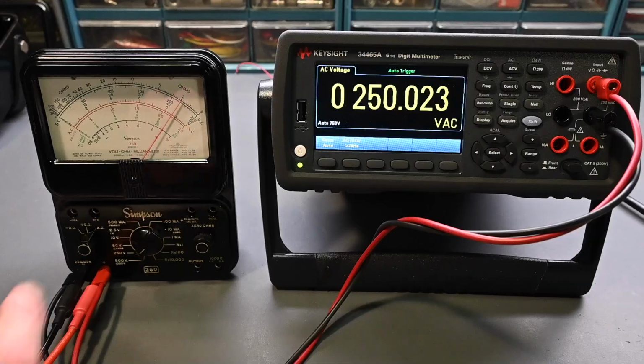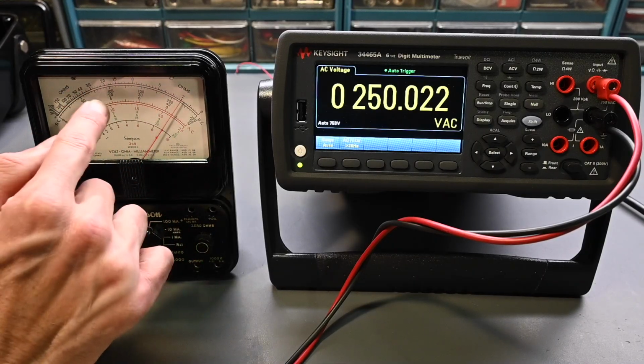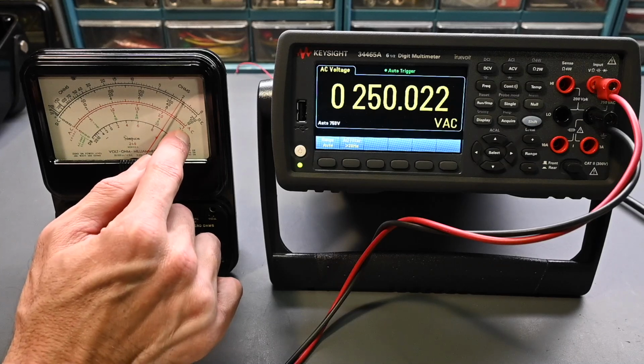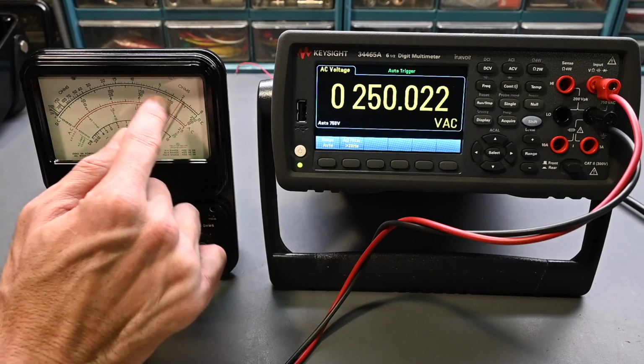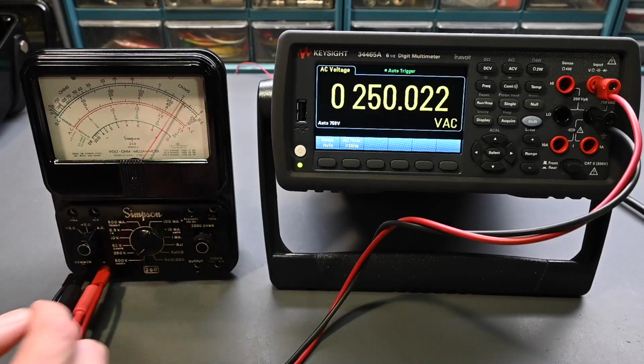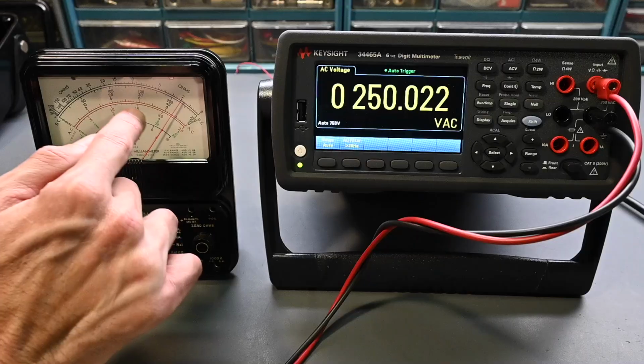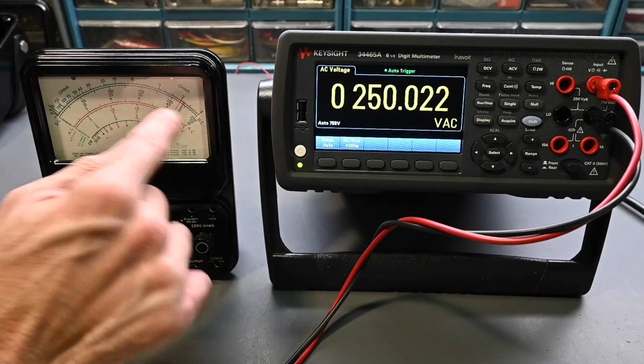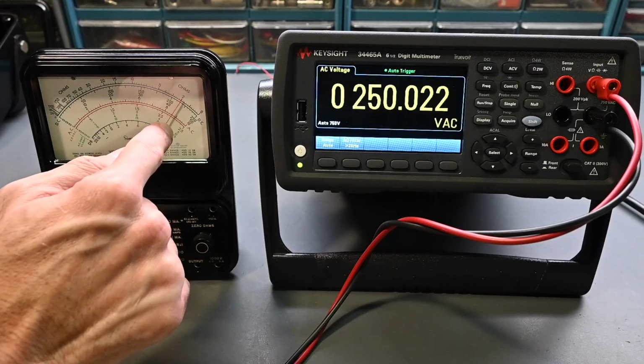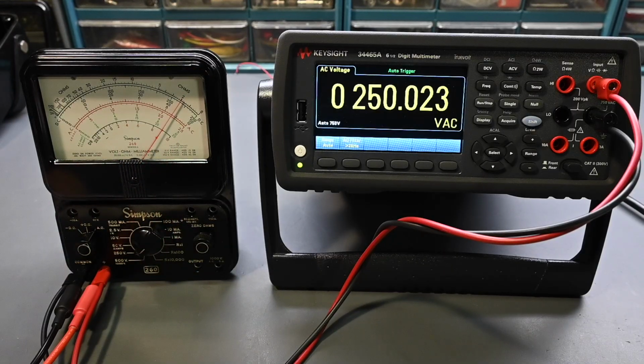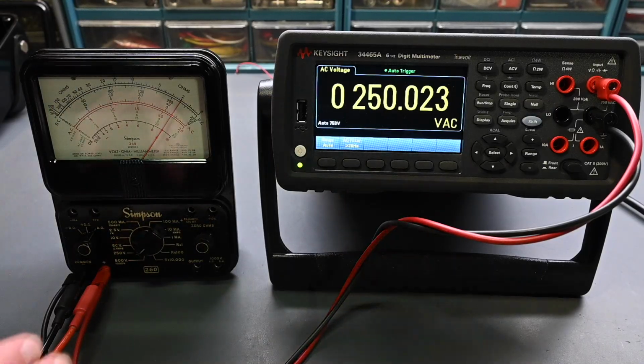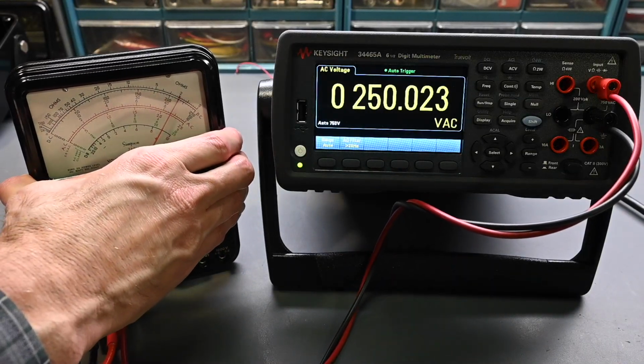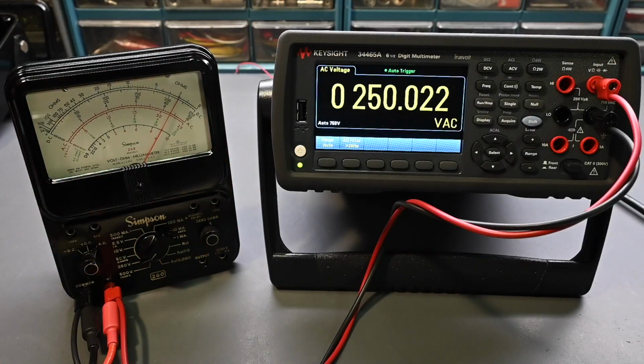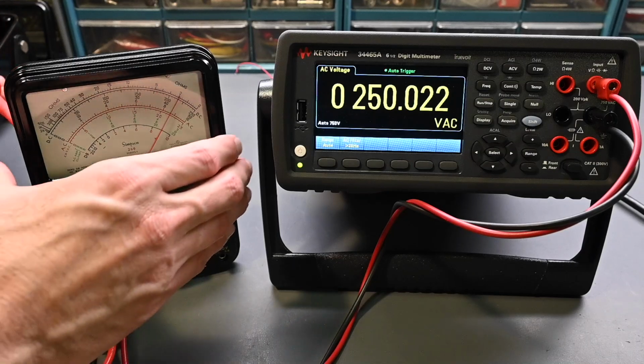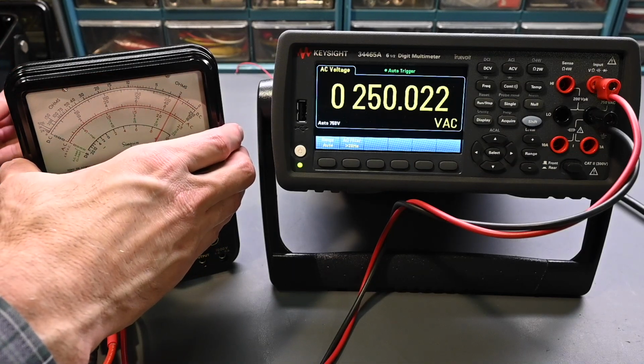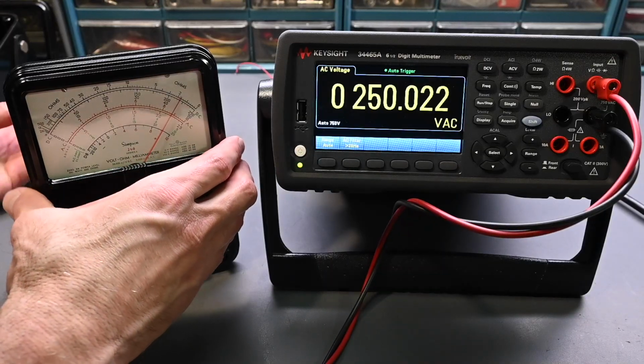Now, don't forget on AC voltage, you're reading these red scales down here. So there's 2 red scales, and for all the voltage ranges except 2.5 volts, you read the upper red scale. The numbers are in black, of course, right there, but you're reading the tick marks on that red scale. And then on 2.5 volts AC, you're reading this lower scale, which is basically shifted off just a little bit in relation to the other scale. So make sure you're looking at the correct scale when you're taking those AC voltage measurements. Okay, so let me go over here and reach around very carefully here. So we want R22. It's all the way here on this edge. There it goes. Okay, it's increasing.